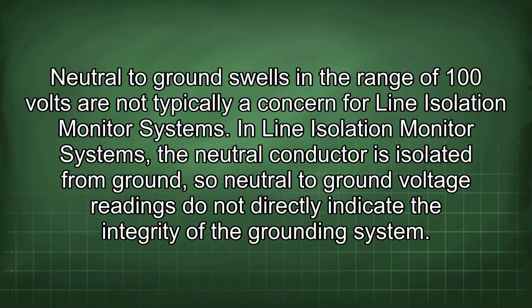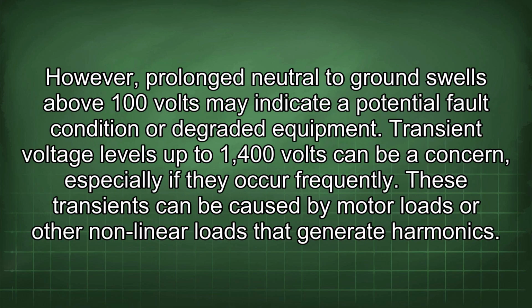Neutral to ground swells in the range of 100 volts are not typically a concern for line isolation monitor systems. In line isolation monitor systems, the neutral conductor is isolated from ground, so neutral to ground voltage readings do not directly indicate the integrity of the grounding system. However, prolonged neutral to ground swells above 100 volts may indicate a potential fault condition or degraded equipment.